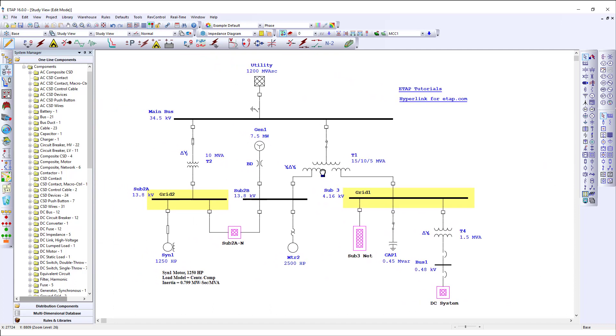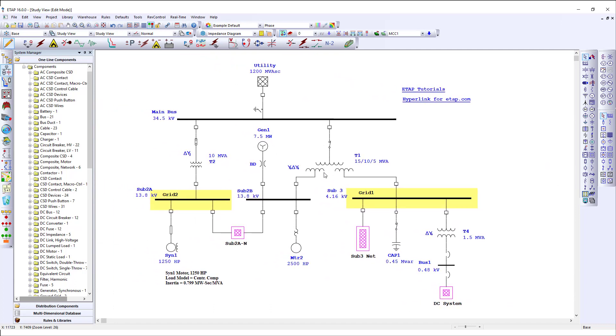Let's move to an existing model to learn how to take advantage of additional features within the ETAP one-line diagram. Another powerful feature for ETAP modeling is the composite network. The composite network, or subnetwork, allows users to model a portion of their project and represent it as a single element, providing a more simple and organized appearance.